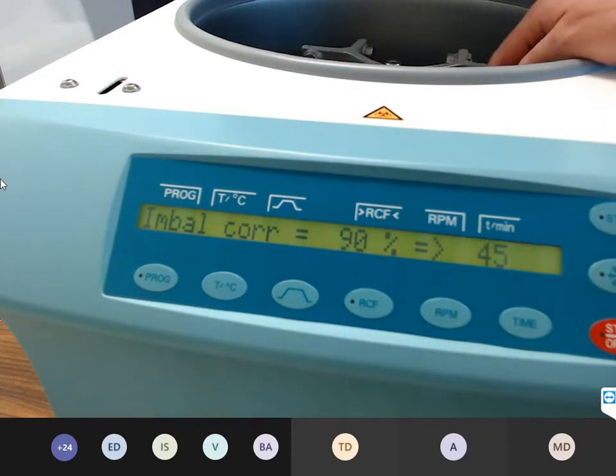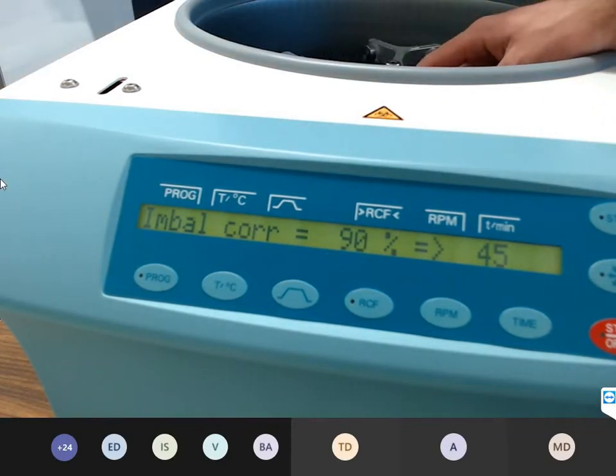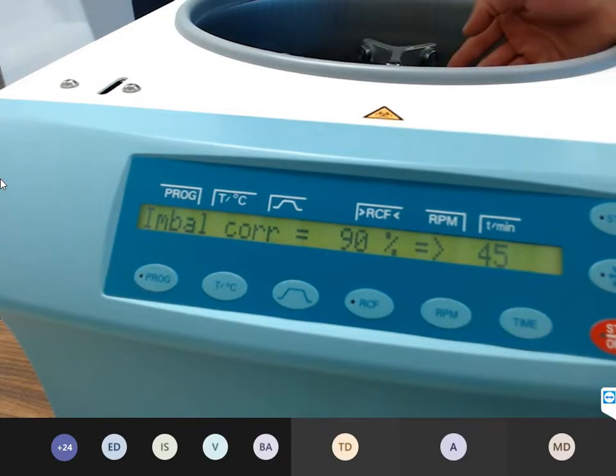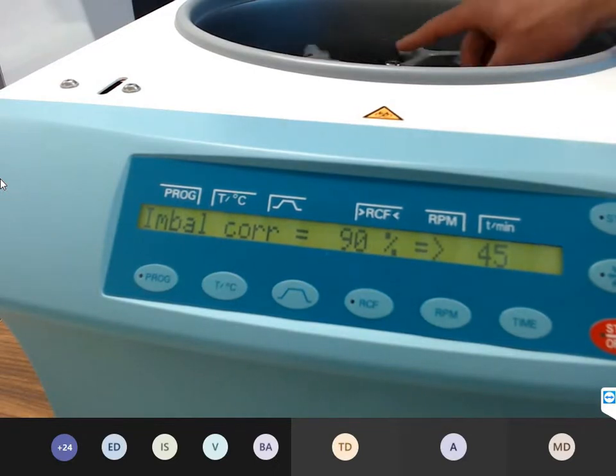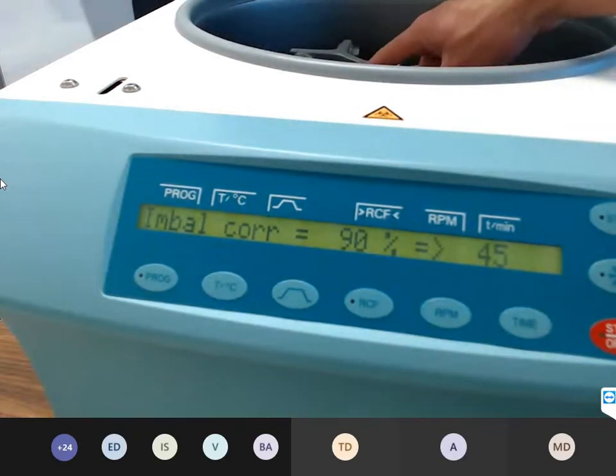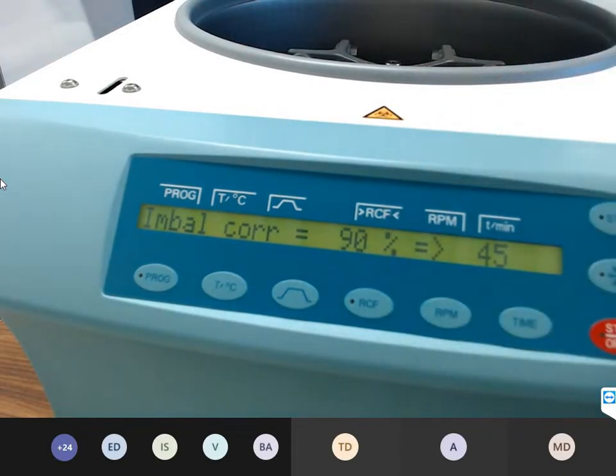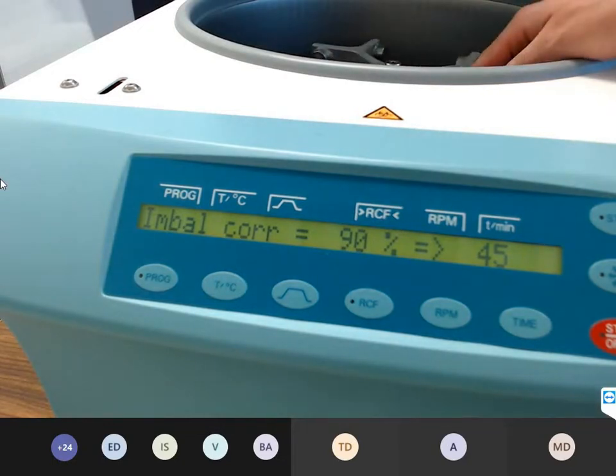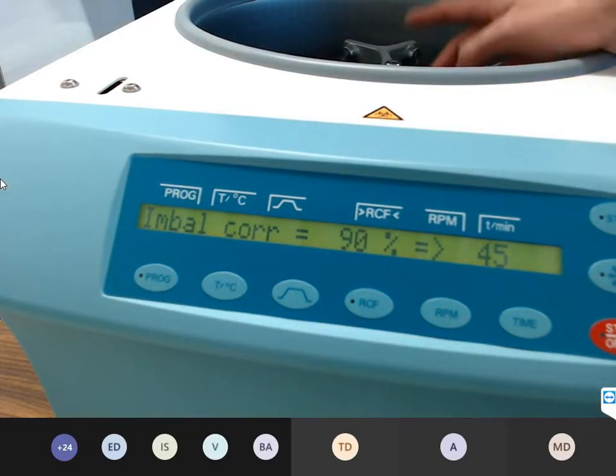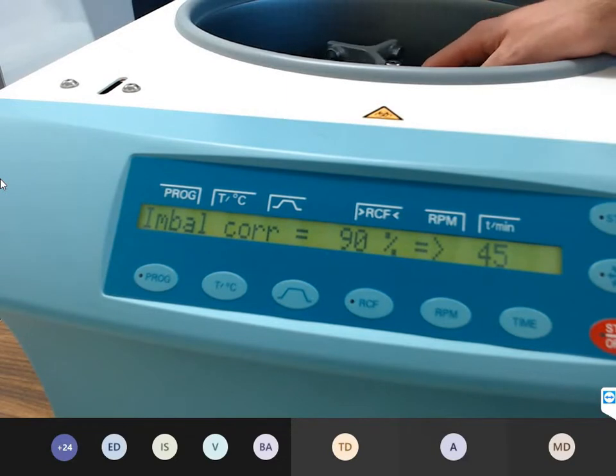We have different imbalance settings, different imbalance values for different rotors. You have to set it for every rotor if the customer uses the imbalance value. The values you can find in the service manual. For example, for this rotor, we say the device must shut off.